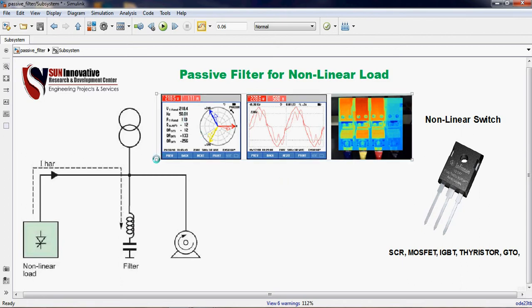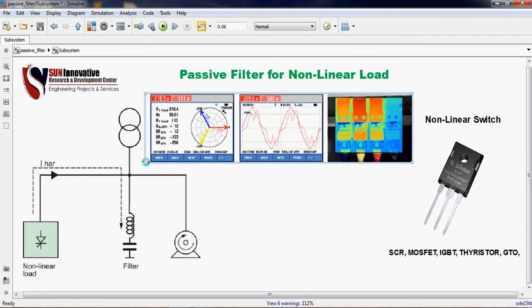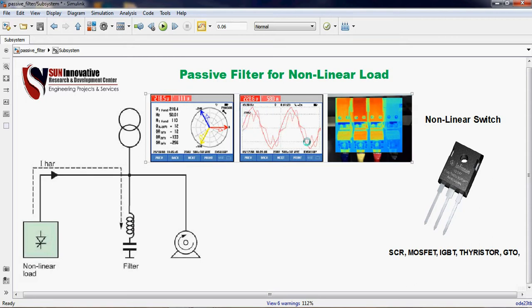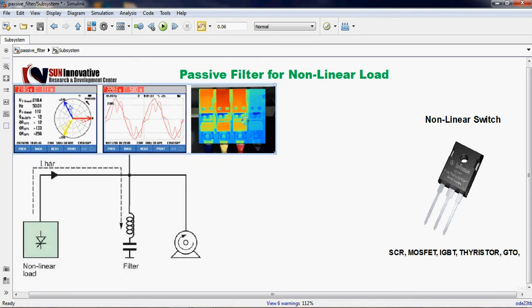Using the clamp meter 435, we have the reading of voltage as well as current. You can see a thermal effect of the wires and filters also here due to the harmonic they get heated up. You can clearly see here the heating of the material.